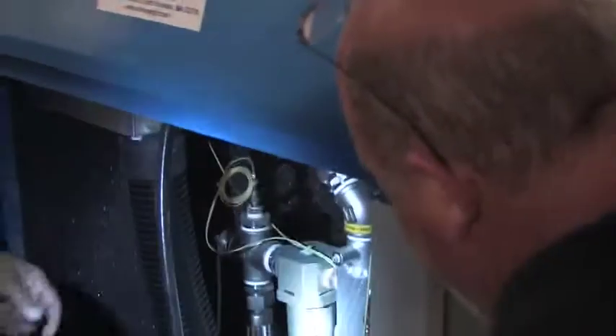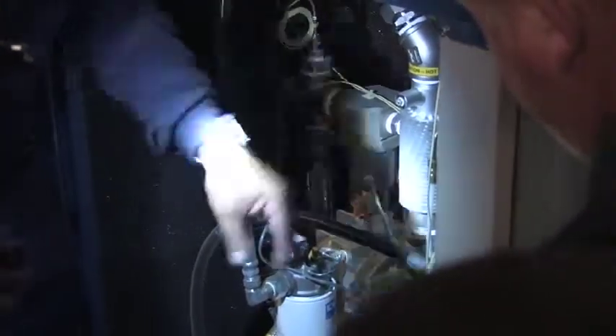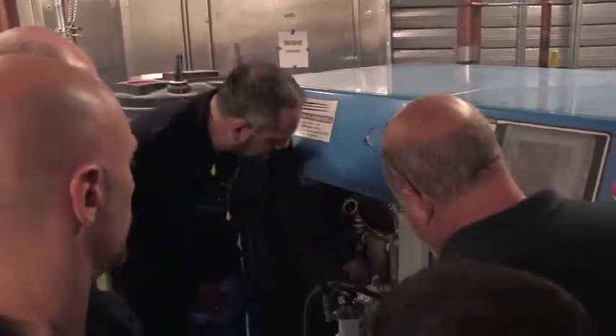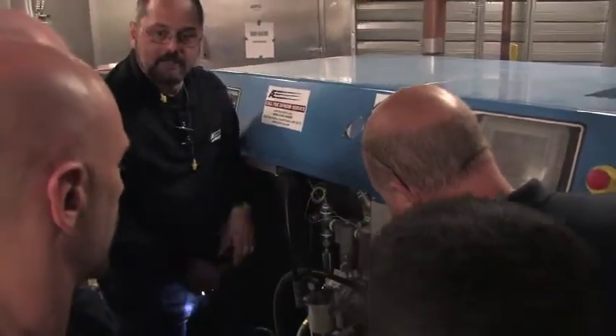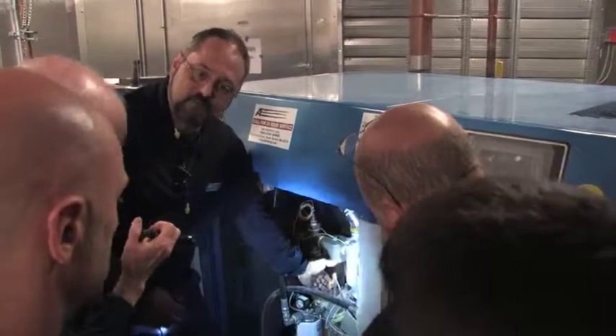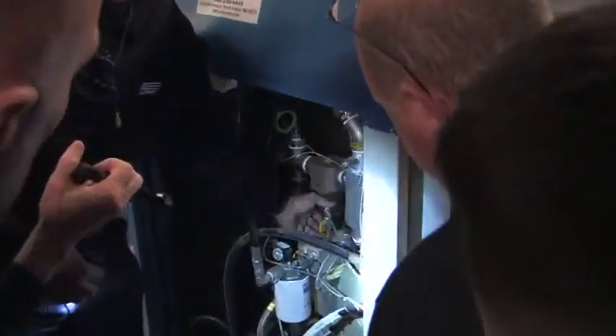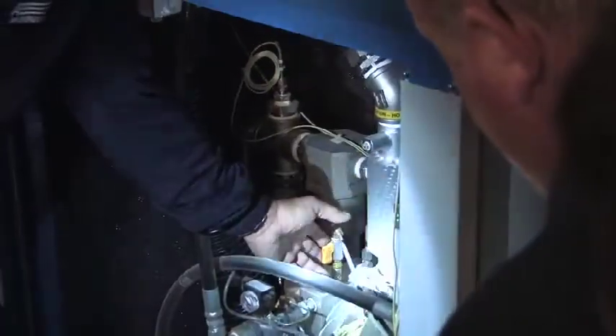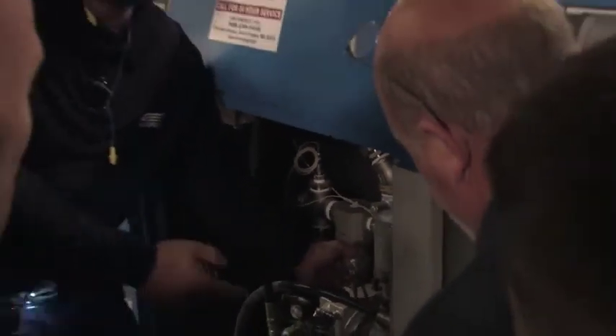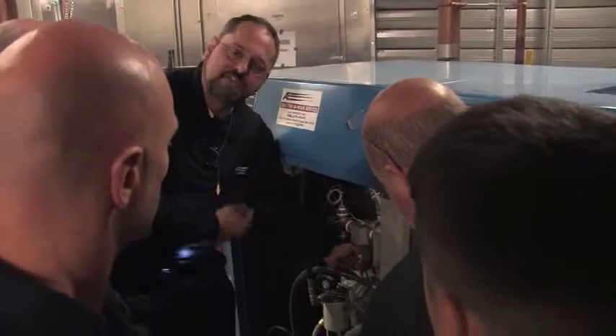It triggers the alarm. If we turn this off and we hit the start button and run the machine, in 10 seconds it'll shut down because of low oil pressure, because this line goes to the oil pressure sensor. The reason for this is people used to test low oil pressure by taking the wires off the contactor, and forget to put them back on. So we don't, even just testing it for 10 seconds.